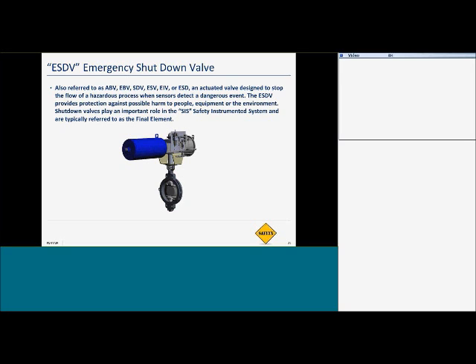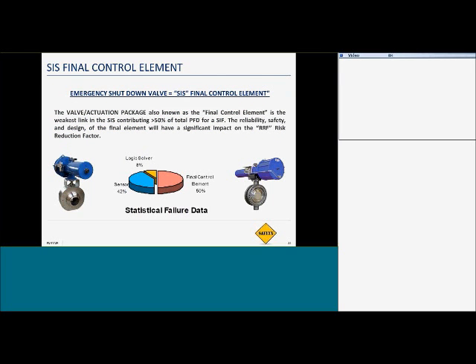So, there's a lot of different acronyms for these, but really they're referring to the same thing, and that is these are all automated emergency shutdown valves. Now, they can be fail open, fail closed. Typically, none of these are ever fail last for SIS. So we're looking at failing these to a position specifically.